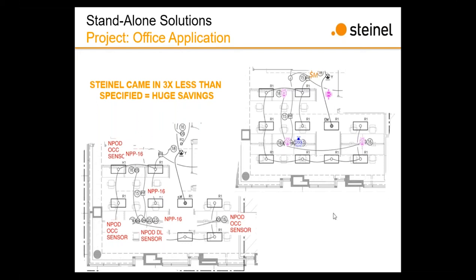Most of our competitors will then require a power pack for each daylight zone. We will not, because our sensors have that 0 to 10 right out of it, so we can control a daylight zone utilizing the specific daylight sensor in that occupancy sensor.